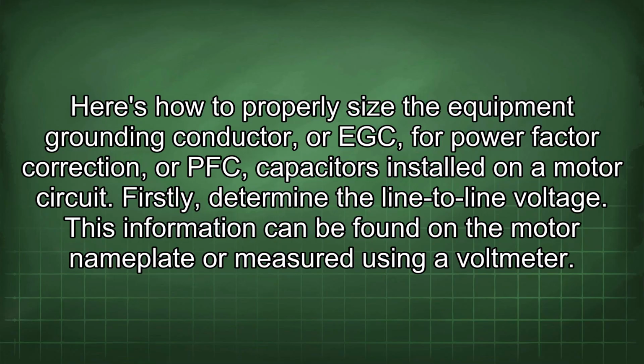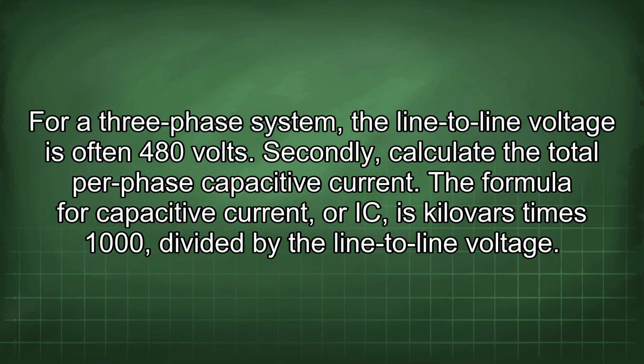Here's how to properly size the equipment grounding conductor, or EGC, for power factor correction, or PFC, capacitors installed on a motor circuit. Firstly, determine the line-to-line voltage. This information can be found on the motor nameplate or measured using a voltmeter. For a three-phase system, the line-to-line voltage is often 480 volts.